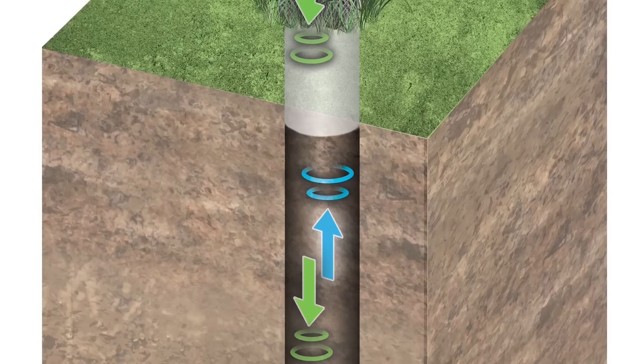The sonic water level meter works by a probe at the surface emitting a low frequency sound wave into a pipe, tube, or well. It measures the time it takes for the pulse to return after making contact with water. The depth to water is calculated using the speed of sound and time. Readings are displayed in just seconds. The sonic water level meter also has a temperature sensor that accommodates any temperature changes.